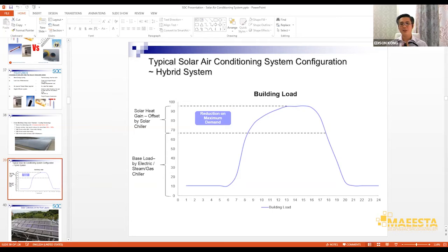Now talking about return on investment, this is also very subjective and varies from project to project. In certain projects, if the existing chiller plant is not efficiently designed, meaning it runs at very high kilowatt per ton, you can enjoy more savings. So the return on investment can range, I think, below 10 years, maybe 8 years, up to even 20 years.